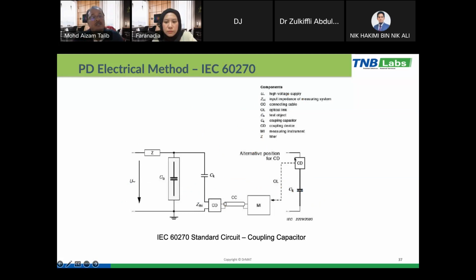Then the other method we can use is the electrical method. This is the setup of the standard PD testing. Not only for the power transformer, but also for the cable, switchgear, GIS, and so on. This is the typical setup for the electrical method in accordance with IEC 60270. So Z, we have a blocking impedance or HV filter, and then we have here Ca. Ca is the test object, and then Ck is a coupling capacitor or divider, and then Cd is a coupling device or matching impedance, and then it goes to the measuring instrument.